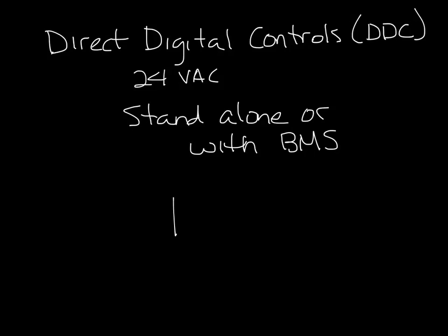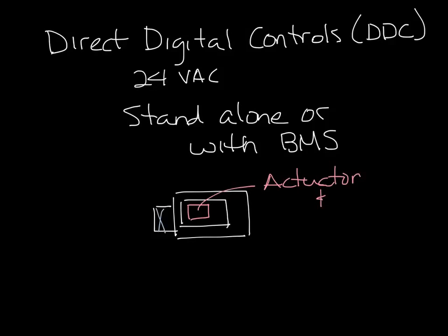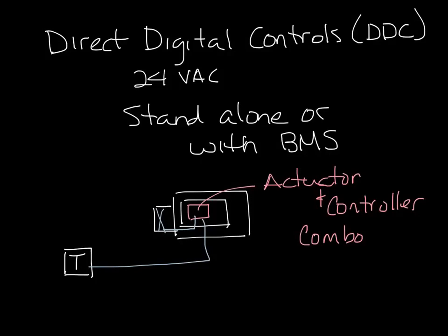So let's draw another single duct box. There's a flow sensor in the inlet, and then you have a controller-actuator combo usually. There are some models that are two parts, but frequently they're one combo unit now. And then a thermostat on the wall somewhere. Again, the thermostat is connected and the flow sensor connected to the controller, which drives the actuator.